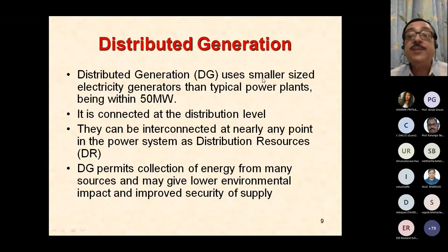Distributed generation uses smaller size electricity generators than typical power plants, being within 50 megawatts as per IEEE. This rating may be enhanced soon, but this is what we have right now. Distributed generation is typically around 50 megawatts. But that does not mean that a single solar power plant cannot be more than 50 megawatt, or the total power injected into a distribution network cannot be more than 50 megawatt. No, we can have multiple 50 megawatt power injection points into the same grid, at suitable points, and we can support the local grid from all these resources that we have from the solar. And of course, it is connected at the distribution level, and they can be interconnected at nearly any point in the power system as distribution resources.